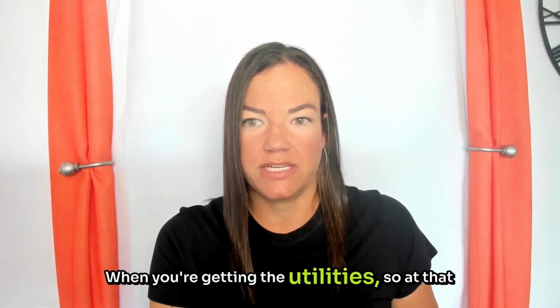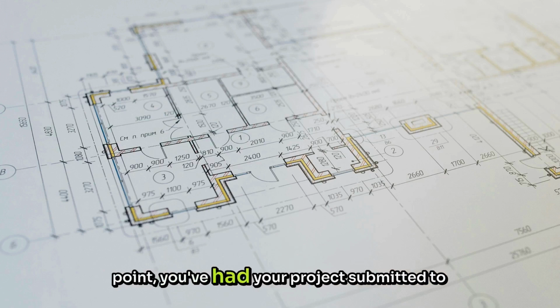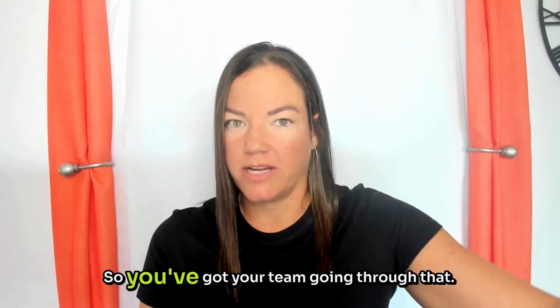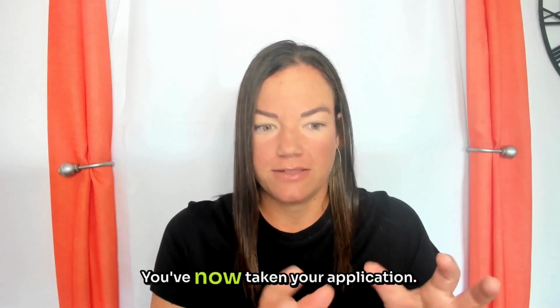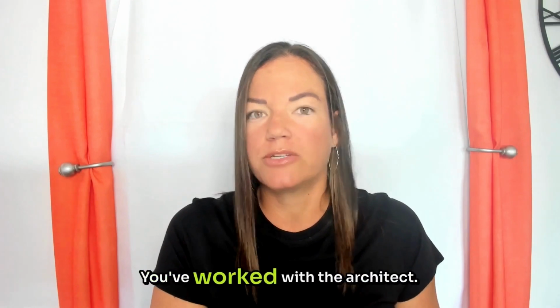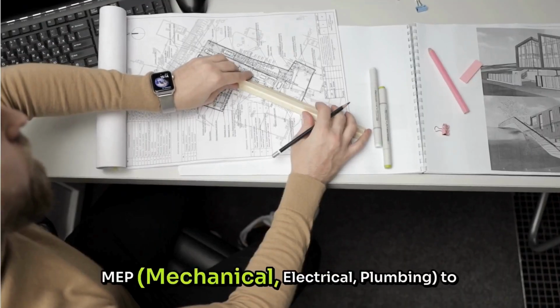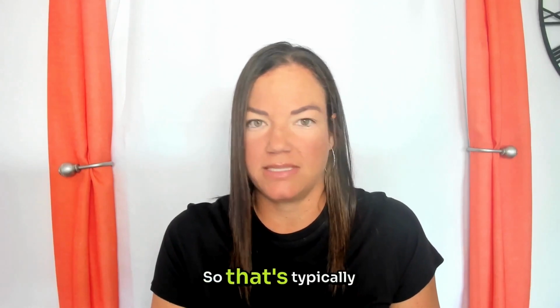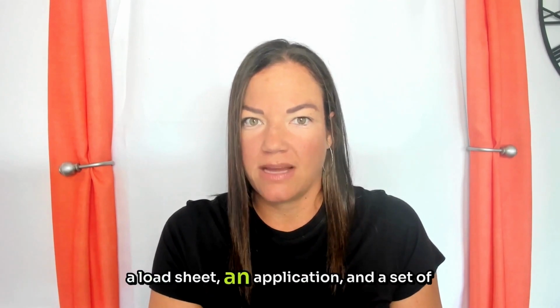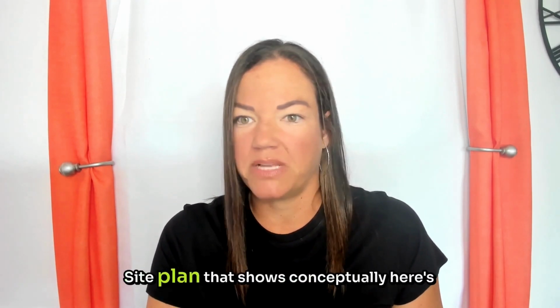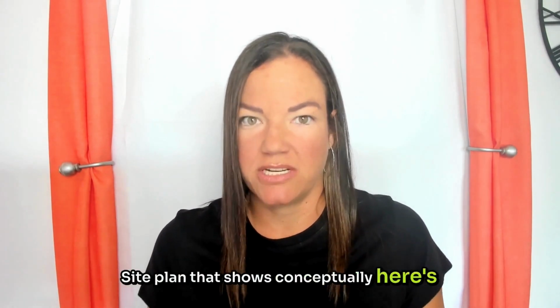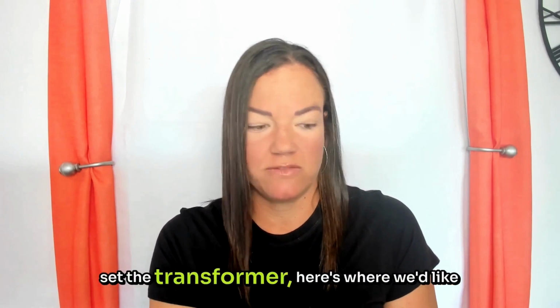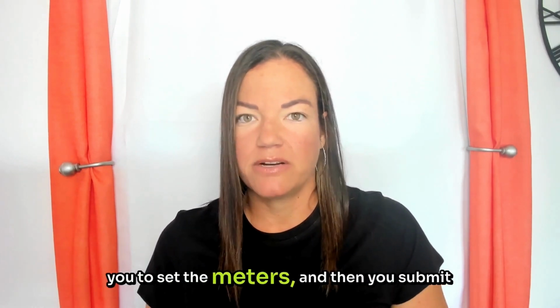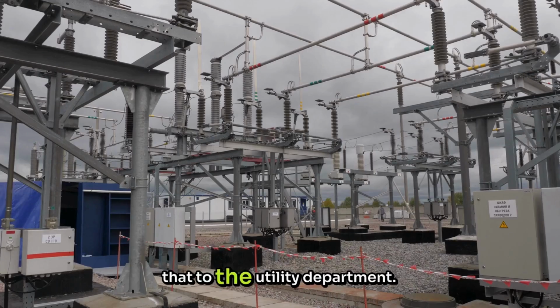When you're getting the utilities, at that point, you've had your project submitted to the city. So you've got your team going through that. You've now taken your application. You've worked with the architect. You've worked with the MEP to prepare the application. So that's typically a load sheet, an application, and a set of plans. Site plan that shows conceptually, here's where it's at. Here's where we'd like you to set the transformer. Here's where we'd like you to set the meters. And then you submit that to the utility department.